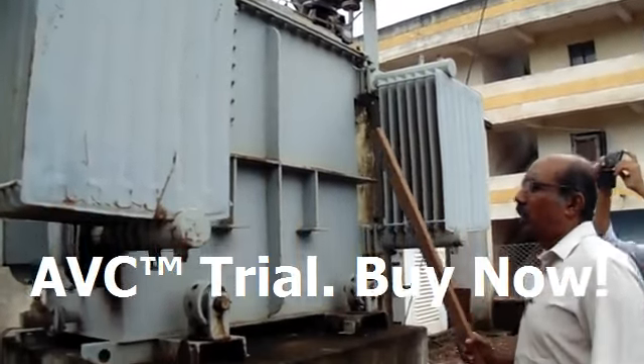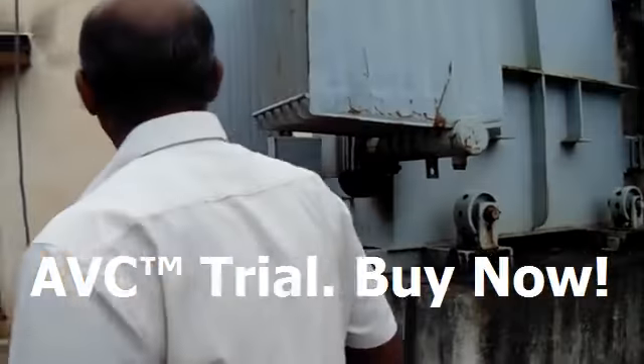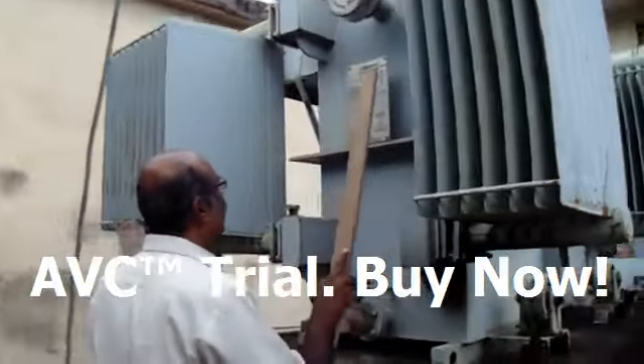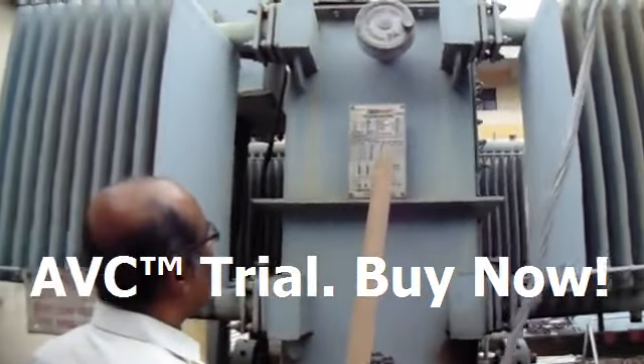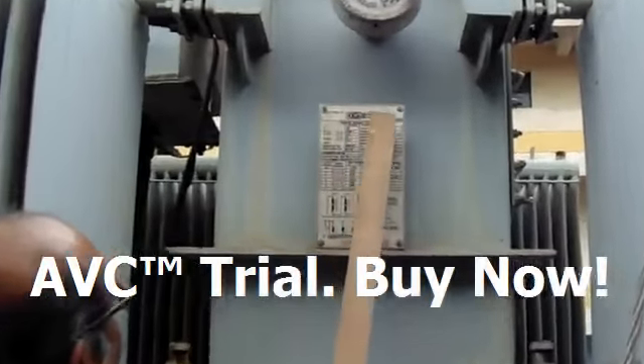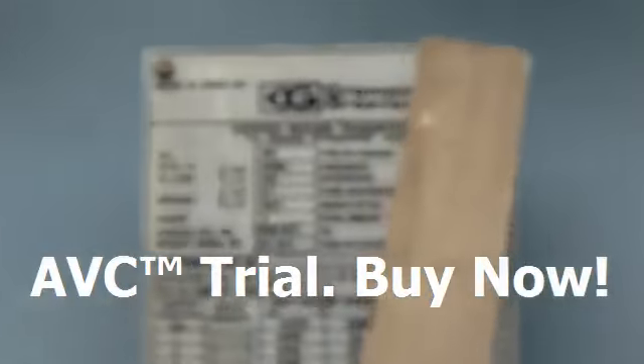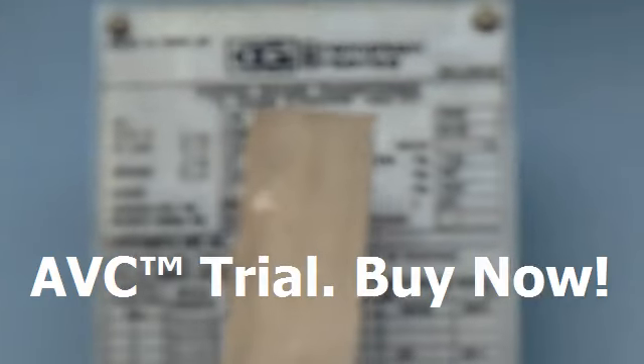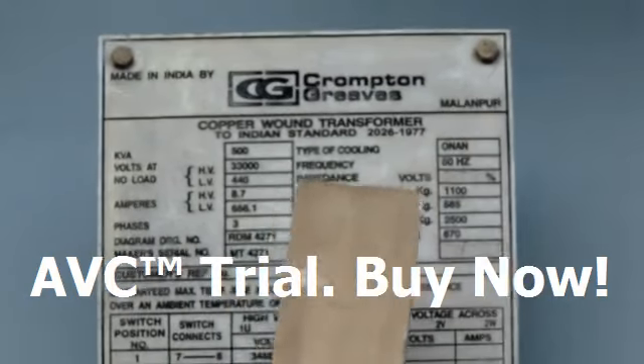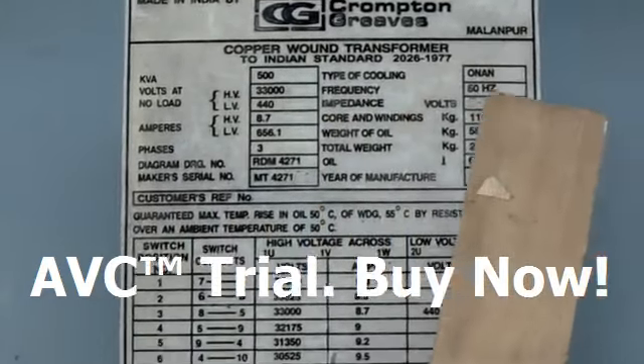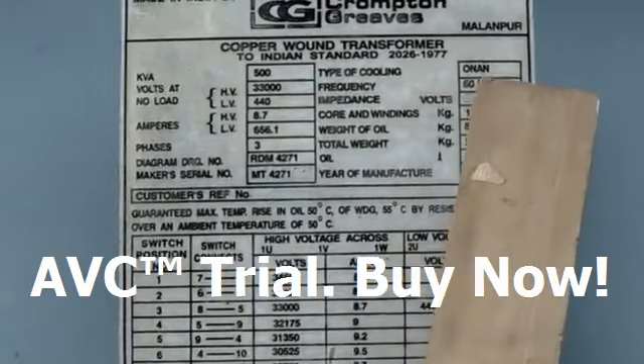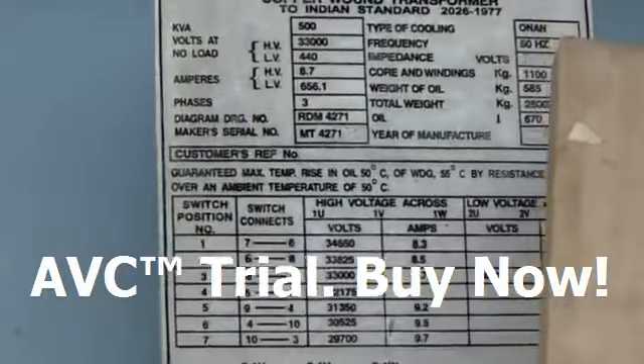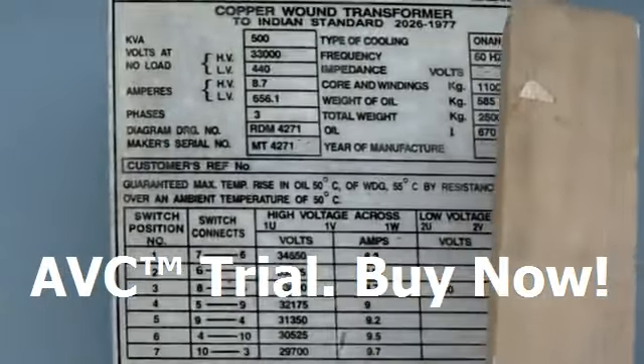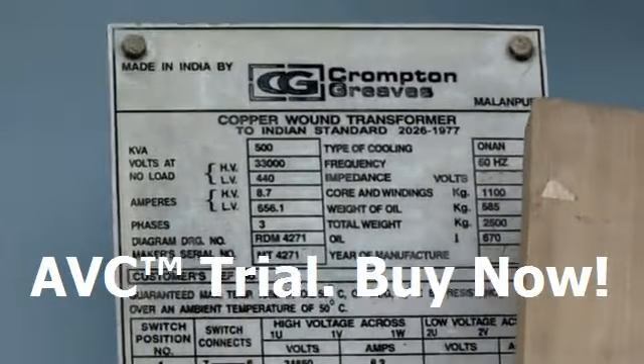Fine. Now, the most important thing when you come to the transformer is seeing the specification sheet or the specification details of the transformer. With this transformer, you can see that it is made by Crompton Greaves, and the rating of this transformer is 500 kVA, the HV rating is 33 kV, and the LT rating you can see is 415 V. For 415 plus minus, the deviation is given, that means plus 10% it can go or minus 15% it can go down.